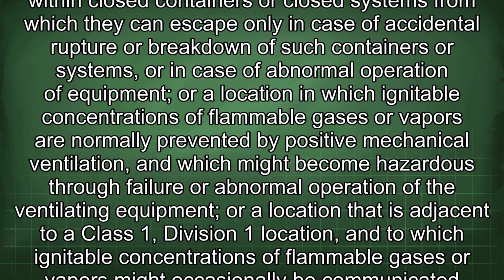Secondly, Division 2: a location in which ignitable concentrations of flammable gases or vapors are handled, processed, or used, but in which the liquids, vapors, or gases are normally confined within closed containers or closed systems from which they can escape only in case of accidental rupture or breakdown of such containers or systems, or in case of abnormal operation of equipment, or a location in which ignitable concentrations of flammable gases or vapors are normally prevented by positive mechanical ventilation, and which might become hazardous through failure or abnormal operation of the ventilating equipment, or a location that is adjacent to a Class 1, Division 1 location, and to which ignitable concentrations of flammable gases or vapors might occasionally be communicated unless such communication is prevented by adequate positive pressure ventilation from a source of clean air, and effective safeguards against ventilation failure are provided.